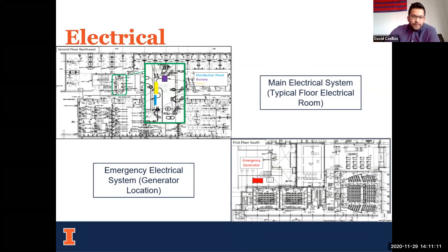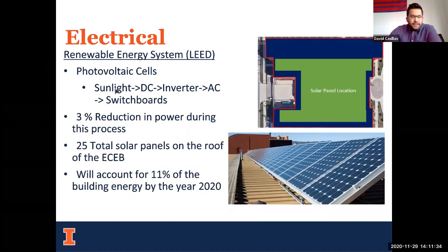For a typical floor, there are two electrical rooms—this one is on the north side, and there's another on the south side with basically the same orientation. This is the distribution panel, coming from the unit substation up to the floors, connecting to a busway, which connects to the panel, which then leads off, as you can see in this line, to the individual room panels.